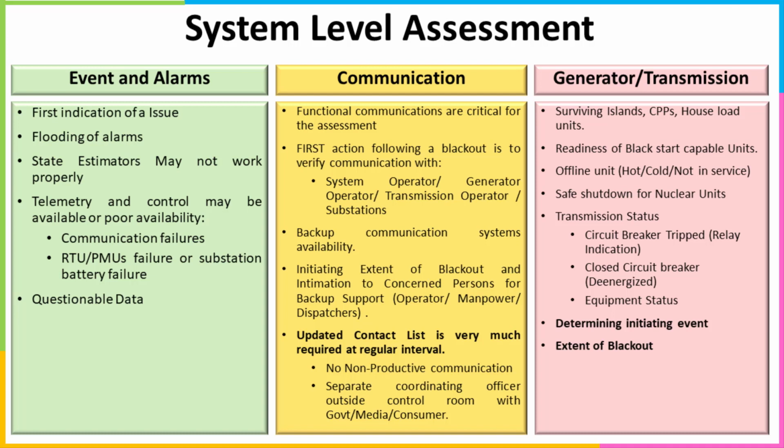So those will take a lot more time for bringing back into the system. Then you have to look into hot and cold, whether we have a hotter start or whether you have to go for a colder start of those units. And one important aspect, if there is a nuclear power plant involved, then you have to go for a safe shutdown process so that there is no poisoning of the reactors. So that should also be taken care of. You have to supply a minimum amount of power immediately so that they can shut down safely.